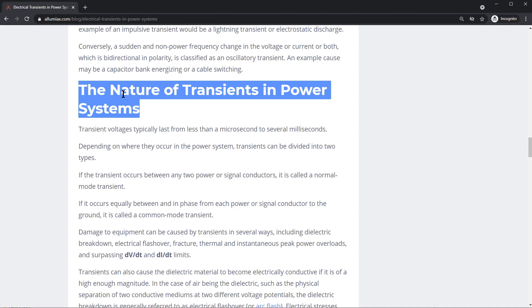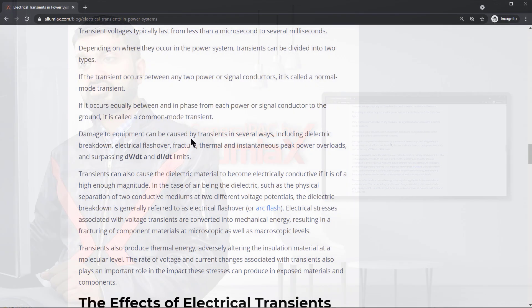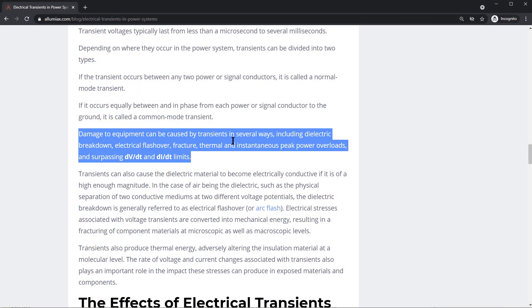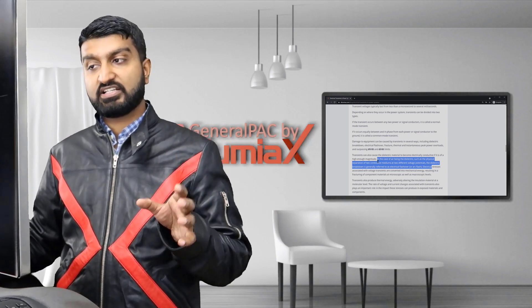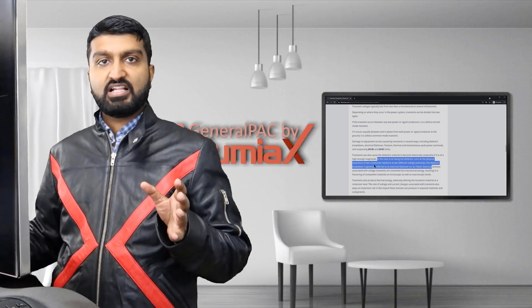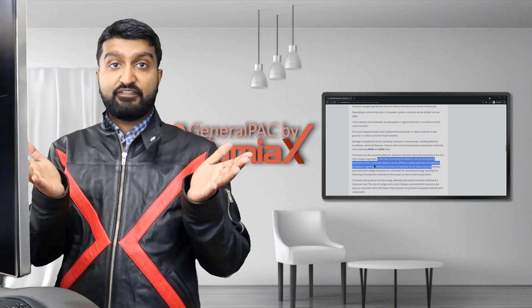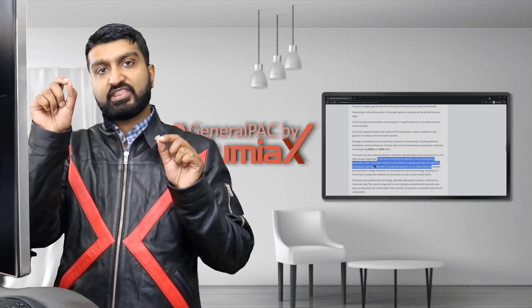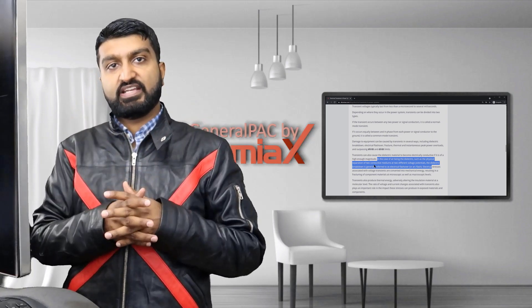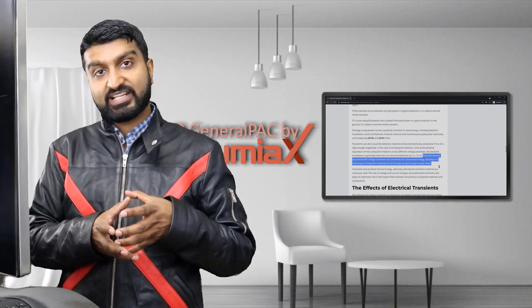Damage to equipment can be caused by transients in several ways, including dielectric breakdown, electrical flashover, fractures, thermal effects, and instantaneous peak power loads. There is a dielectric medium that can experience flashover between two separate phases, and when insulation breaks down, a conductive path forms from one phase to the next.